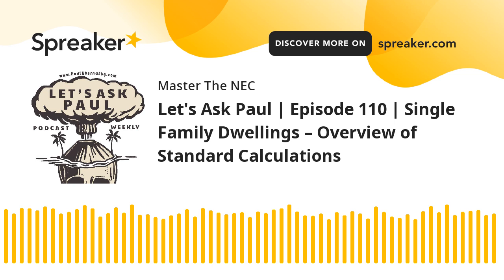That's how this works for the 2020 when you're doing that comparison, okay? It's just an exercise. Don't overthink it, okay? Do your first comparison and then determine whether or not the one that's the lesser happens to have the largest motor in the dwelling. If it does, do the calculation again. Take that largest motor at 125%, plus the other motors associated with it, and now compare it to the heat again. If it overtakes the heat, then you go with the AC. If it still doesn't overtake the heat, you keep the heat. That's all you're doing here, folks, okay? All right, pretty straightforward, right? All right, don't want to overthink it.